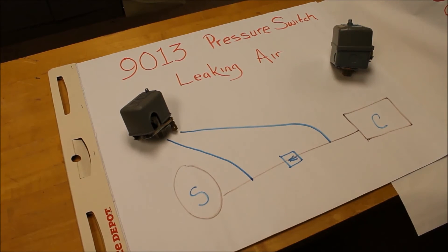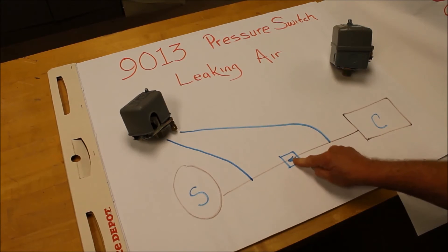This is a continuous cycle that we must stop. The way to stop it is by assuring that the check valve is installed in the correct position and is functioning correctly without being jammed open by debris or scale in the pneumatic line.